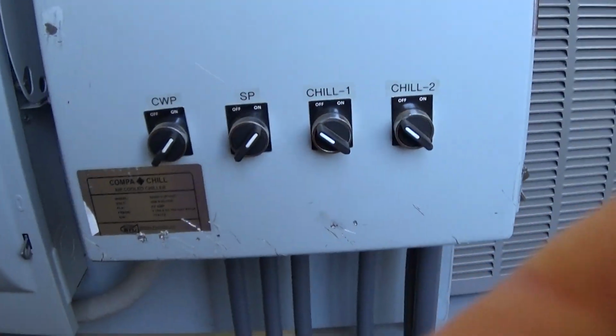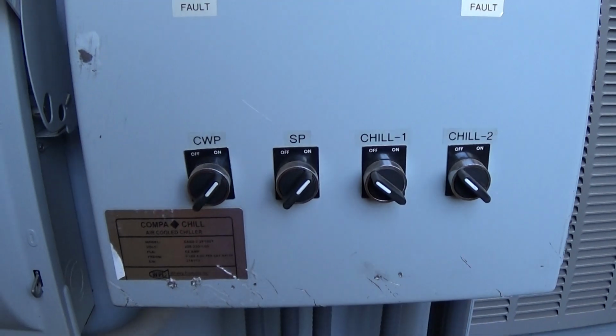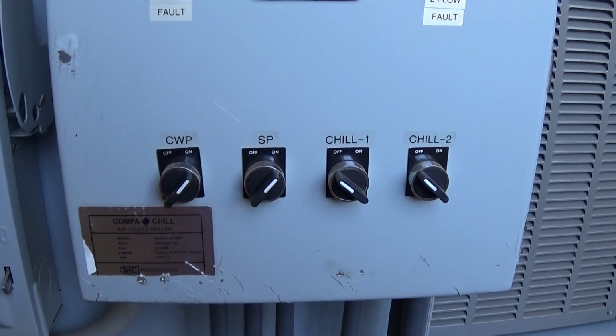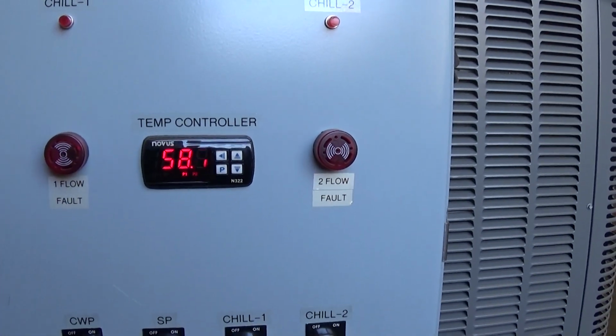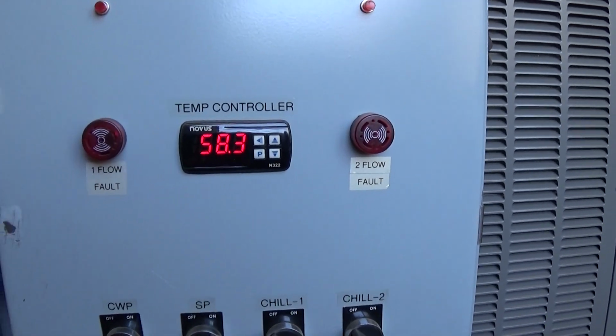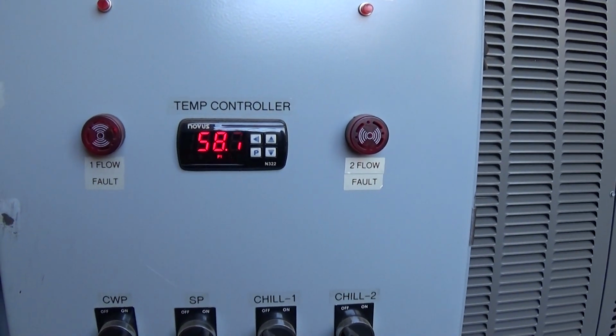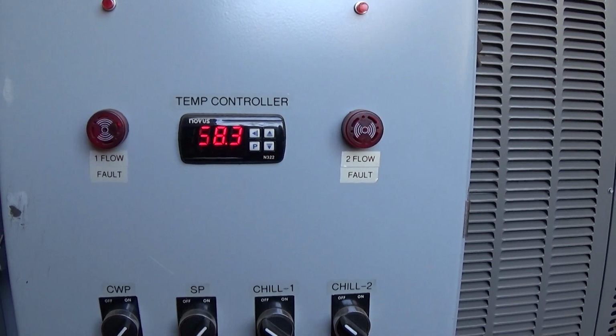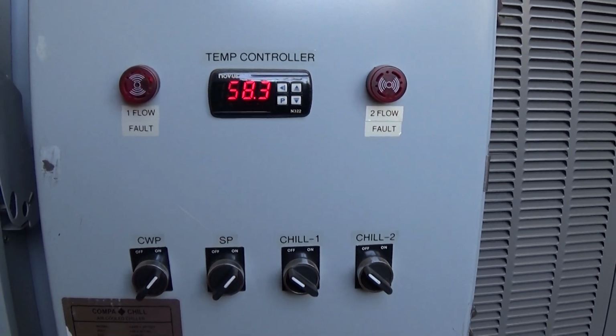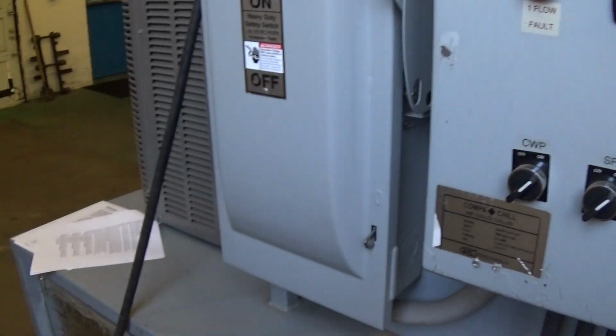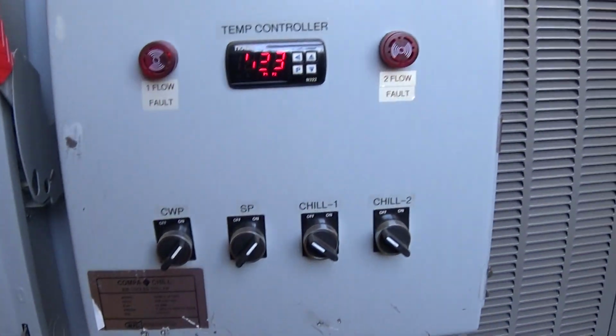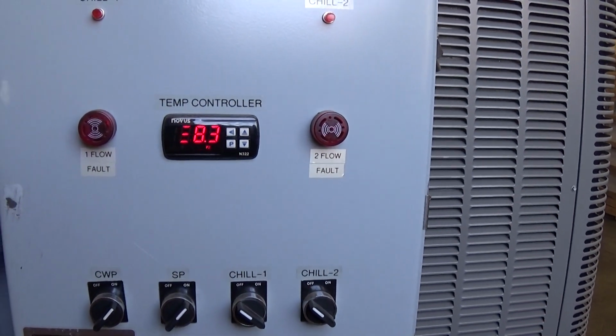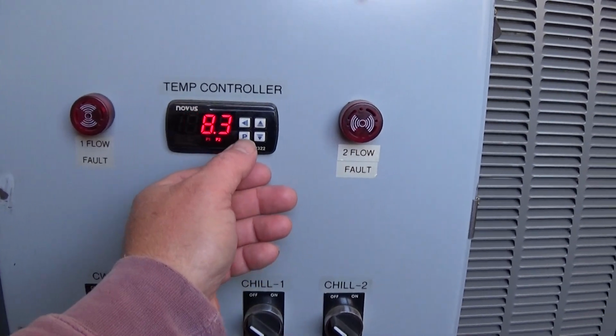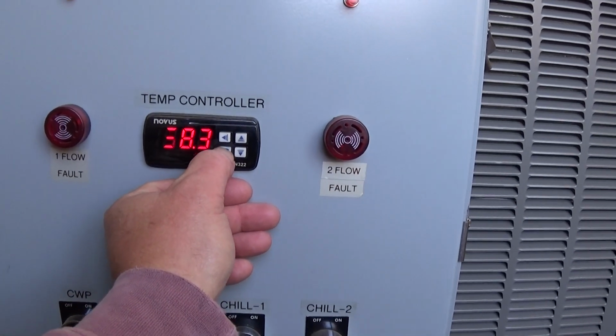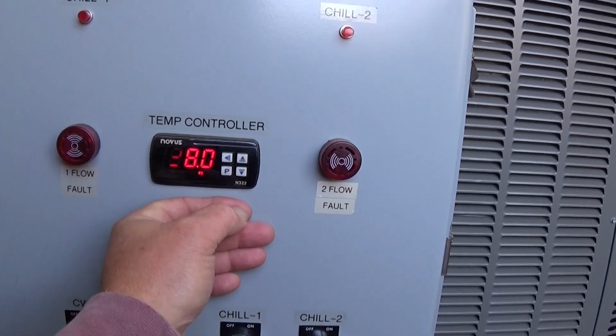So you have to turn at least the chilled water pump on for the controller to power up here. And it's just going to show you what the glycol temperature is right now. The controller is very simple, and the manual is actually very, very good. We sent a link on it. For your set point temperature, you just press P once. And that gives us set point 1.